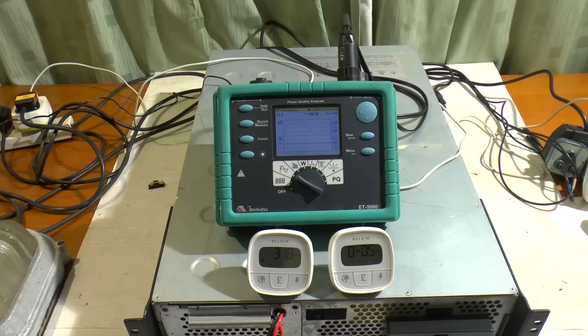And it's gone. So they're definitely on their last legs. One final test on this actually. This is with the batteries disconnected. The UPS hasn't realised the batteries are disconnected yet. It'll start bleeping when it realises they're unplugged. But the power consumption, assuming the batteries are fully charged and it's not even trickle charging, is about 30 watts.